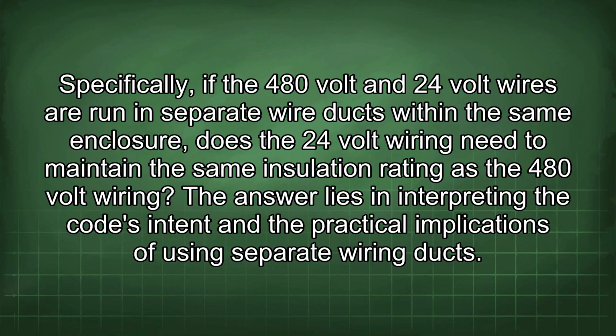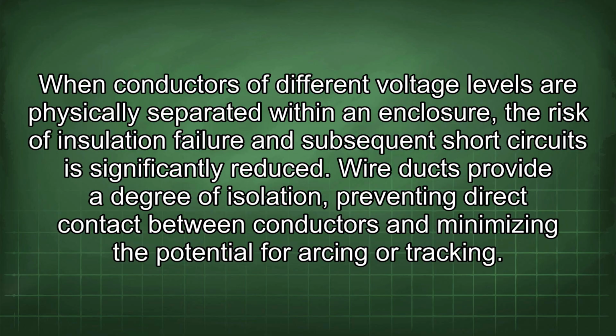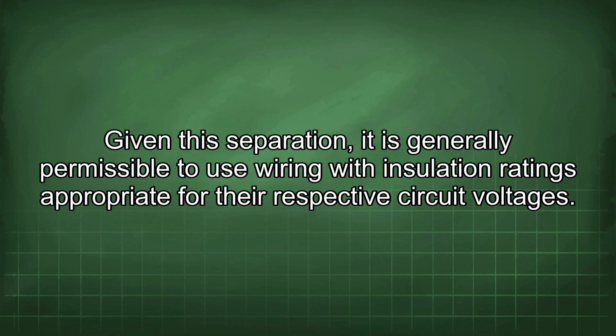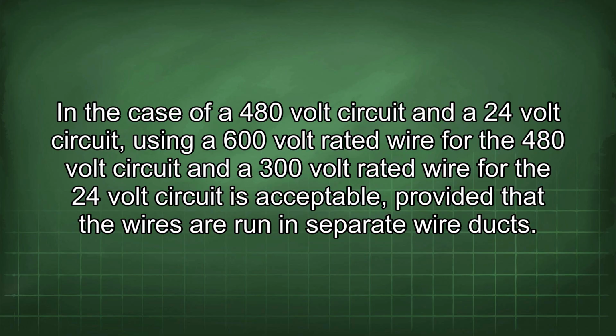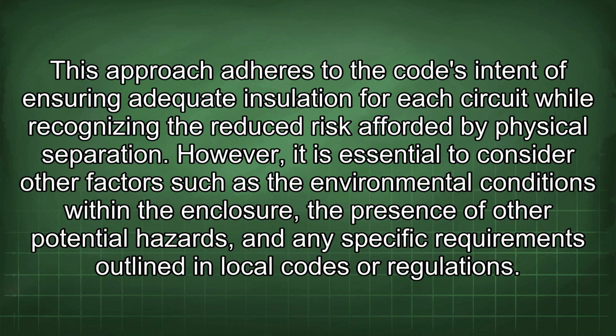The answer lies in interpreting the code's intent and the practical implications of using separate wiring ducts. When conductors of different voltage levels are physically separated within an enclosure, the risk of insulation failure and subsequent short circuits is significantly reduced. Wire ducts provide a degree of isolation, preventing direct contact between conductors and minimizing the potential for arcing or tracking. Given this separation, it is generally permissible to use wiring with insulation ratings appropriate for their respective circuit voltages. In the case of a 480-volt circuit and a 24-volt circuit, using a 600-volt rated wire for the 480-volt circuit and a 300-volt rated wire for the 24-volt circuit is acceptable, provided that the wires are run in separate wire ducts. This approach adheres to the code's intent of ensuring adequate insulation for each circuit while recognizing the reduced risk afforded by physical separation.